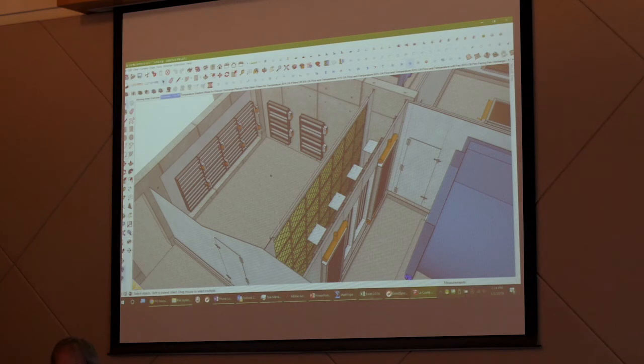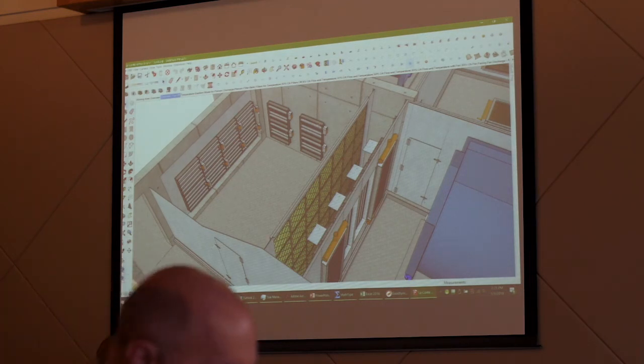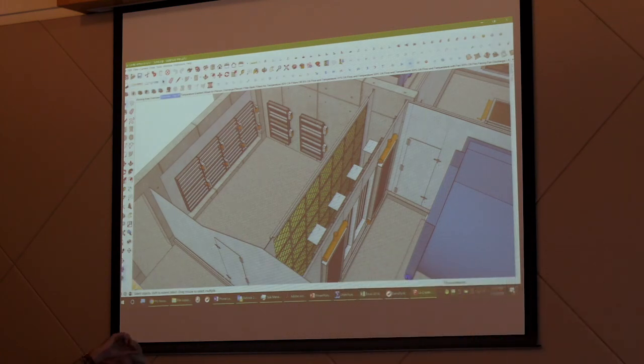So now, just looking at that, if you've been around economizers, there's a pretty obvious clue that this one might not work very well. Does anybody know what that is? Yeah, so you're on the right track. What's the clue you're seeing? Just the different sizes. Yeah, that's it exactly. The dampers are way different sizes. So what that means is these dampers are going to have a totally different characteristic curve than these dampers. And if you look at damper characteristic curves, I could show you some, but they aren't linear anyway, unless you size them really tight, and even then they aren't linear. They're kind of linear, okay?